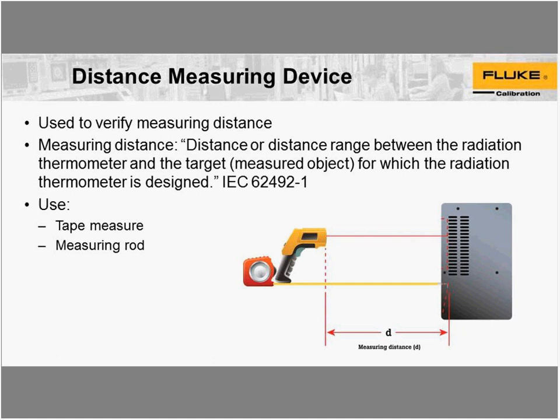For your calibration, you need a distance measuring device to verify measuring distance. Some IR thermometers tend to be more reliant on measuring distance than others. If you have the IR thermometer too close to the target you may have problems, and too far away you start losing your field of view on your thermal radiation source. These devices are dependent on the so-called calibration geometry — measuring distance: the distance or distance range between the radiation thermometer and the target measured object for which the radiation thermometer is designed.